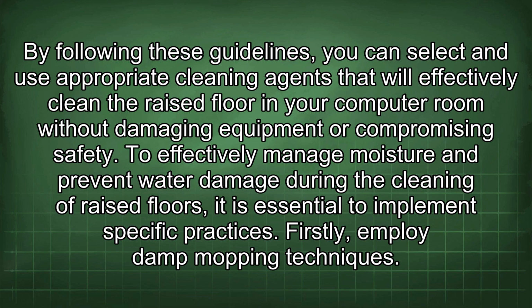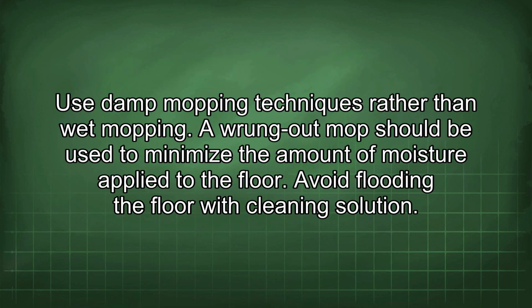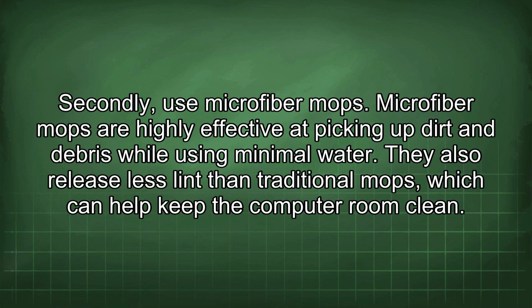To effectively manage moisture and prevent water damage during the cleaning of raised floors, it is essential to implement specific practices. Firstly, employ damp mopping techniques. Use damp mopping techniques rather than wet mopping. A wrung-out mop should be used to minimize the amount of moisture applied to the floor. Avoid flooding the floor with cleaning solution. Secondly, use microfiber mops. Microfiber mops are highly effective at picking up dirt and debris while using minimal water. They also release less lint than traditional mops, which can help keep the computer room clean.